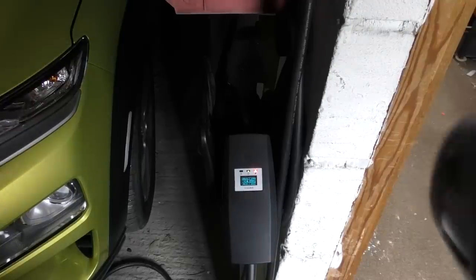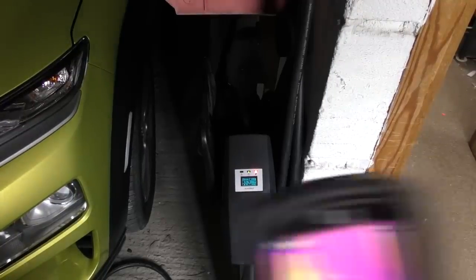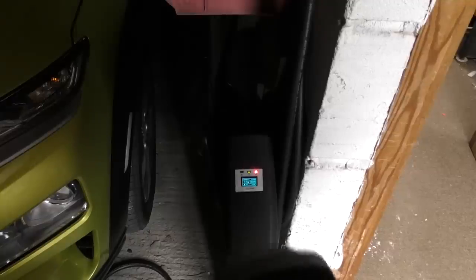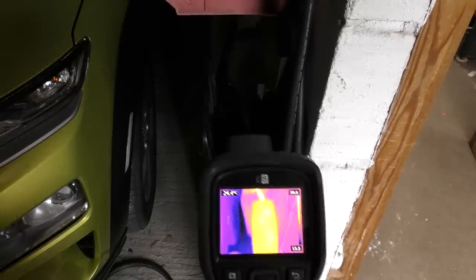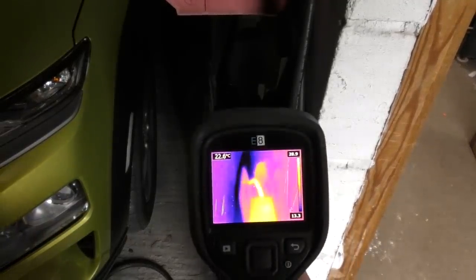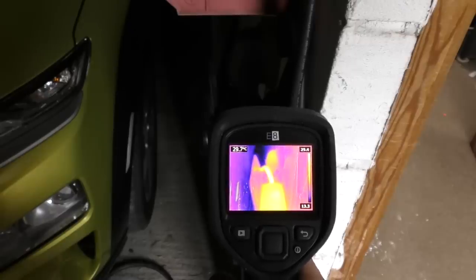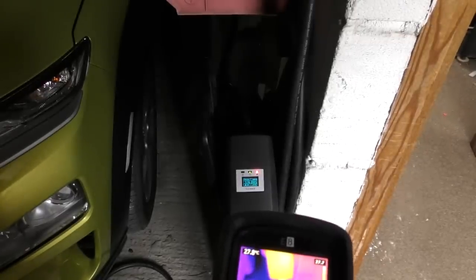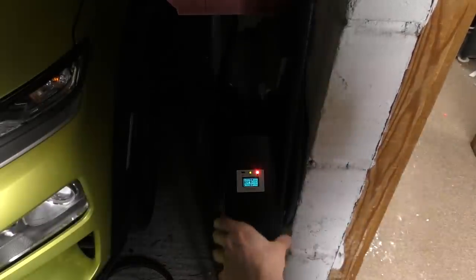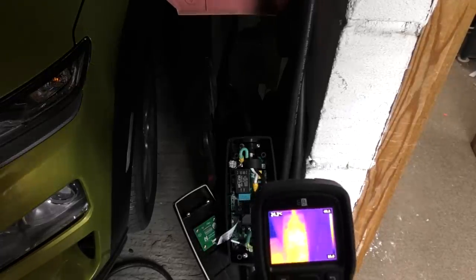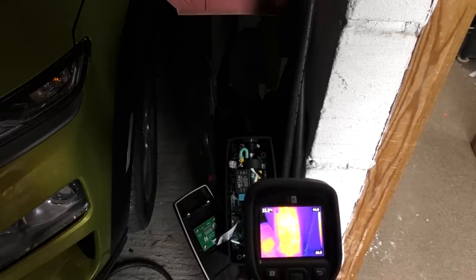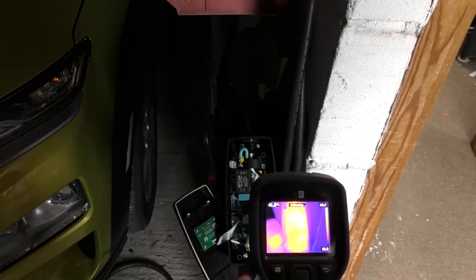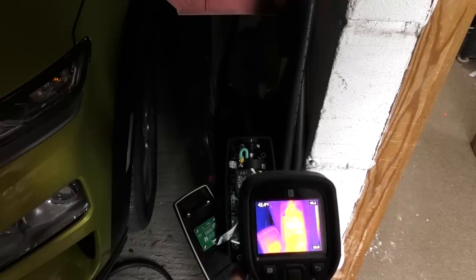So let's just check for heating. This has been charging at 32 amps for about half an hour. The onboard display is saying 33 degrees C, case is 25, input lead 29. Output 27, and internally the relays and the connections 35 degrees, which is fine. Power supply modules about 42.